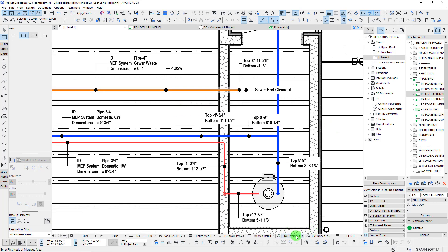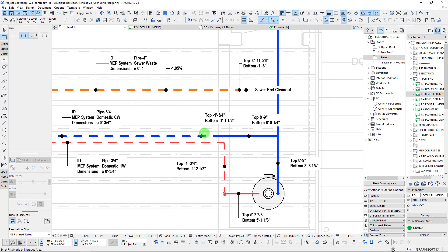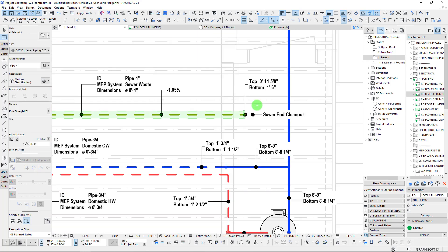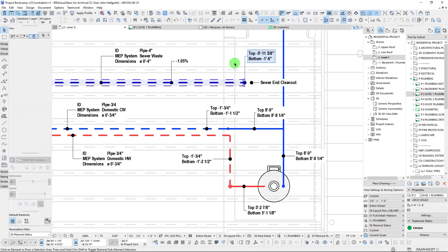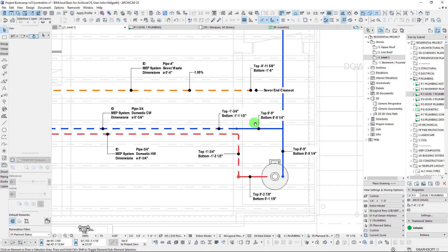The cool thing with this graphic override is when we turn it on, not only does it fade out elements we don't want to see, it also overrides the center line pen — in fact all the pens relating to the plumbing. The ones that are below, which we can see from these labels — for example, the top is about one foot below, the bottom at minus one foot six — confirms it is below, and we can see that's gone to a dashed line. Anything above goes solid. The piping tool changes depending on its elevation.